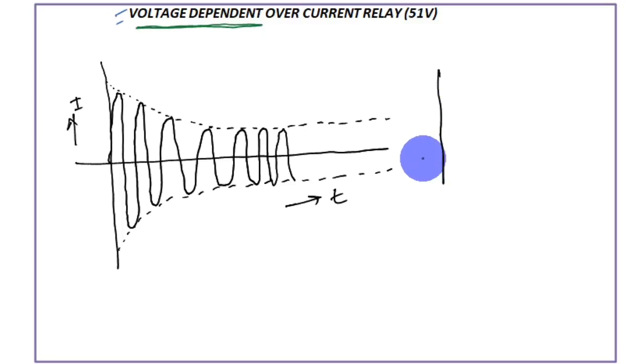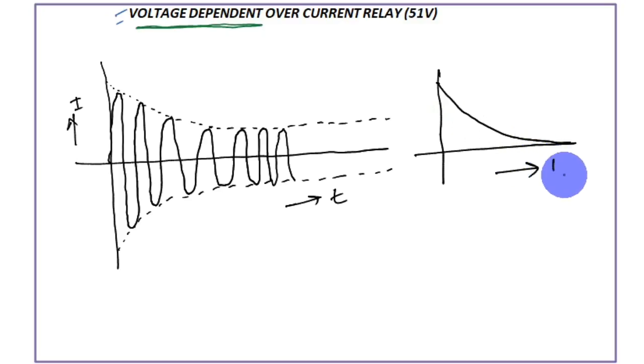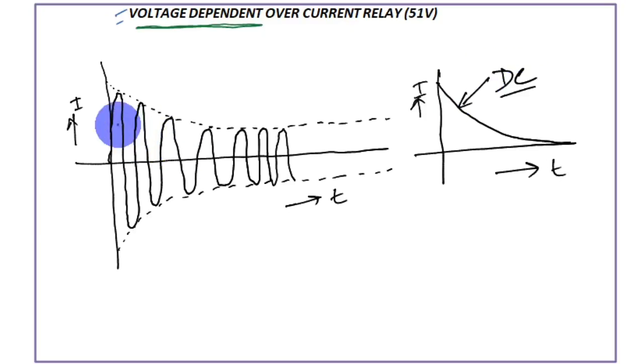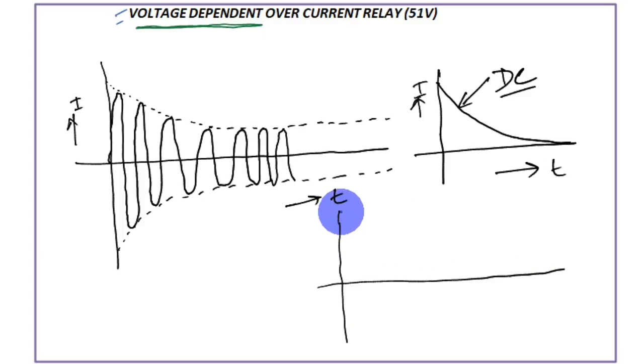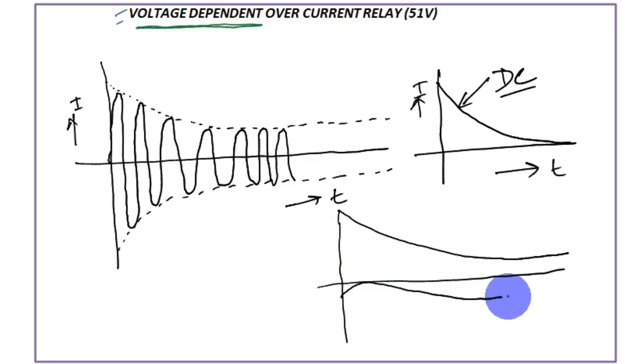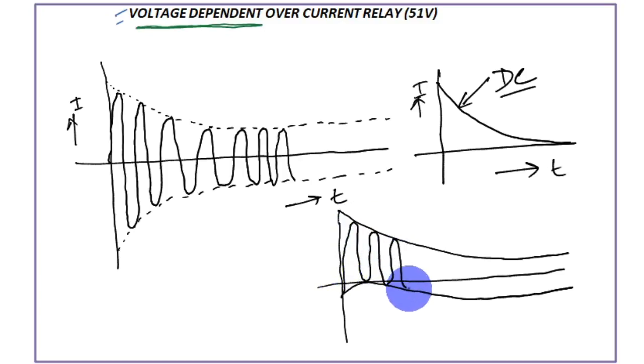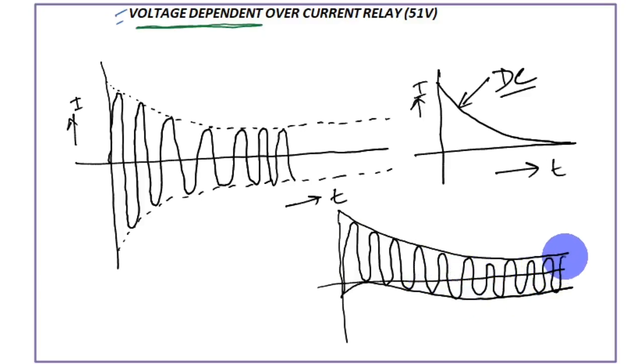There is also a DC component of decaying nature. When this DC component mixes with the symmetrical AC component, the envelope shifts further upward. The resulting combined characteristic is a sinusoidal curve riding on a decaying DC offset, so the overall envelope rises higher initially before settling. This is the generator fault current waveform when a fault happens at the generator terminal.